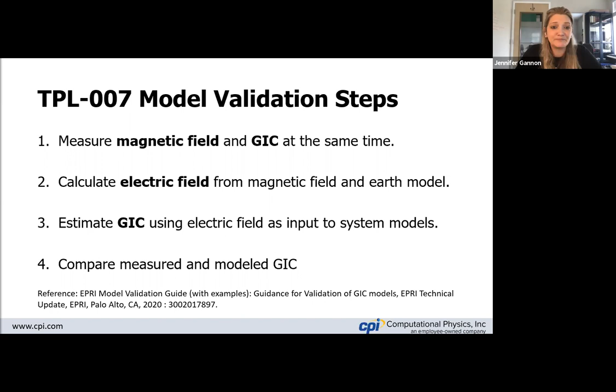There are lots of complications and things to consider when doing GIC measurements as well. But for magnetic field, the best practices are to have 10-second cadence or shorter measurements. Remove spikes and bad data. Most of that's environmental noise, so that goes back to placement of the sensor. A large spike in your magnetic field will give you a false large spike in your electric field, which will give you a false large spike in GIC, and you don't want that. You only want to analyze real information.